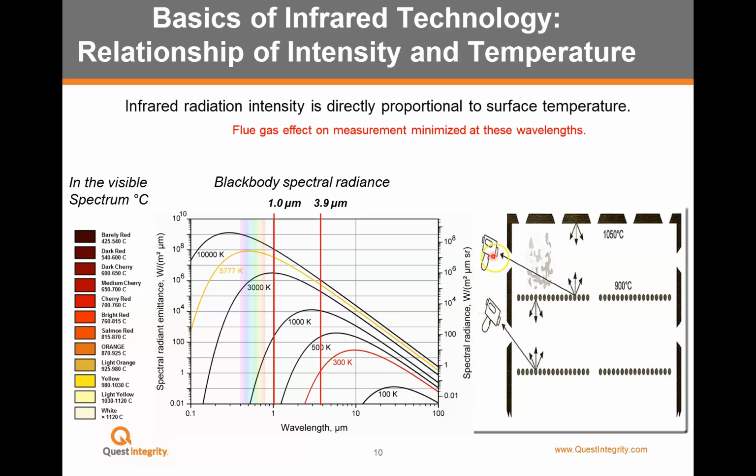As you can see just by looking at this image, we are going to be shooting through flames, which means the total radiation that we get at the camera is going to be affected by the flame patterns and the flue gas patterns. We're also getting reflection from the back wall. We're seeing different angles that we're shooting. So all these factors, plus more that we'll mention, are going to affect the amount of radiation that comes back to the camera or the instrument.